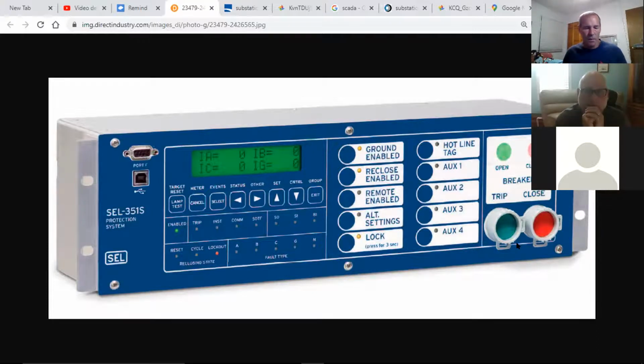Any questions? Now if your trip light is on, is it going to show down in the fault type box? Like if line C was the one that caused the trip—if you've got trip here, right, it's going to scroll through whatever problem you had up at the top. Will it also show it down at the fault type box? Yep, go down, down—that one. It'll show you the phase. So if you have a fault on A phase, it's going to show trip, and A is going to light up.